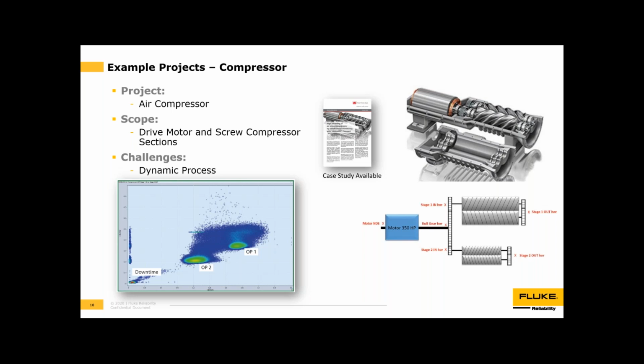You also see down in the bottom left that if the machine's idle, that's where it lives as well. This data is very helpful because you can see where most of this data lives, and any outliers from here should be very easy to detect. This is not a complex FFT or a complex time waveform—just vibration data plotted against a loaded condition.